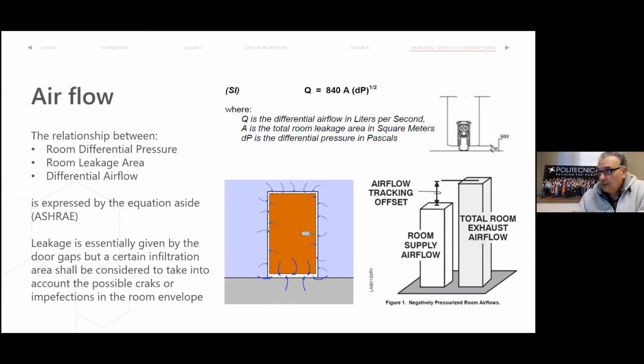So in general, the most important thing to take into consideration is the gap that there is between the door and the frame of the door. So that is the main cause of the infiltration of the air. And according to ASHRAE, the relation that allows you to calculate how much the infiltration is, is given by the equation which is up there. So this is in the international system, of course, liters per second, square meter, and Pascal. Of course, there is even the US units expression, of course, in the same report. There are both. You can see it.